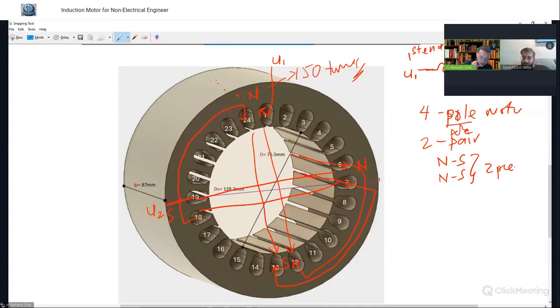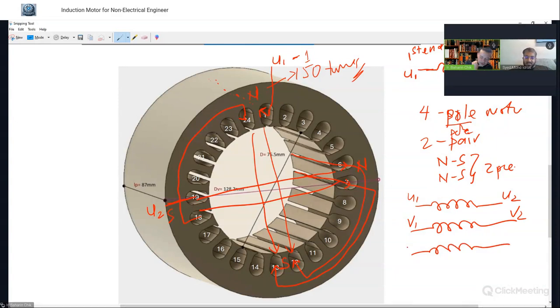Okay, alright. Earlier there was a question asking, does the number of stator slots need to be divisible by 3? Because at the top there are 3, right? Correct. So what we do here is this one is single phase. You know, just one phase. Because in effect we have one phase here, U1 and U2. The other phase is V1 and V2. Now the third phase is actually W1 and W2. So if you put all this winding into the slot, it comes to 24.